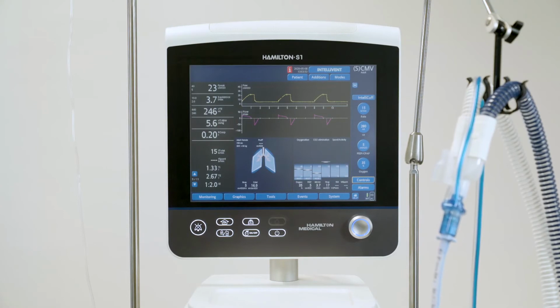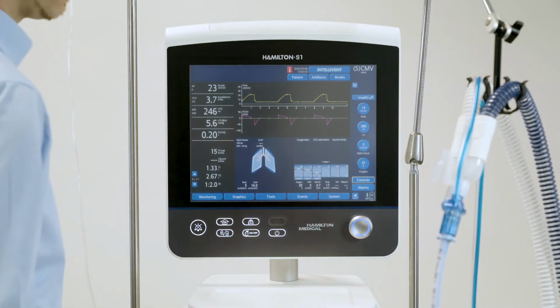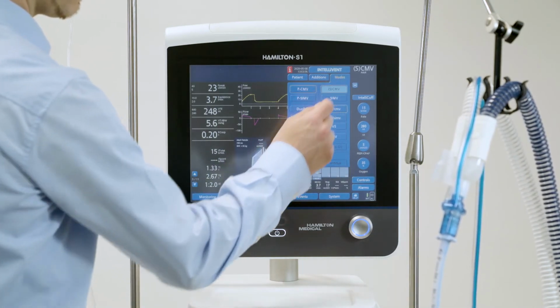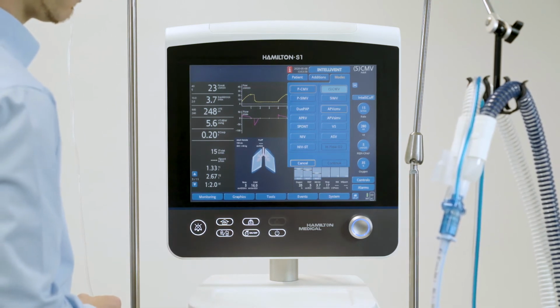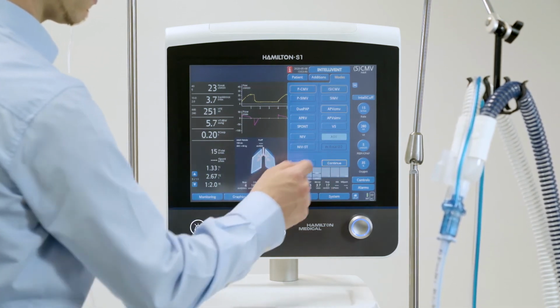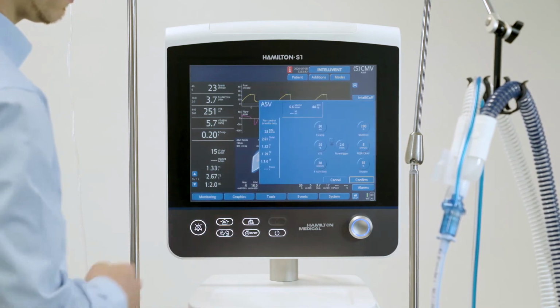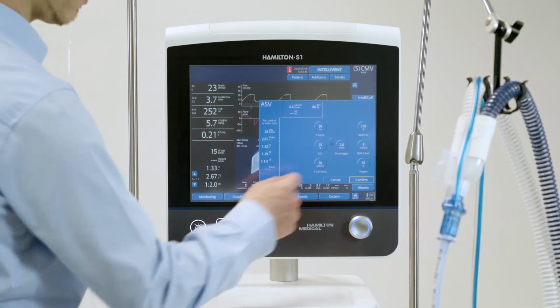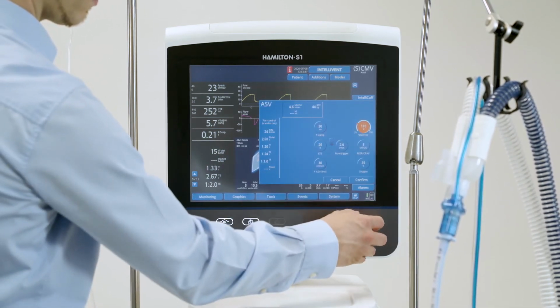If needed, you can change the active ventilation mode. Just select the desired mode and confirm. The Controls window opens. Review and adjust the control settings as needed, and then touch Confirm to activate the new mode.